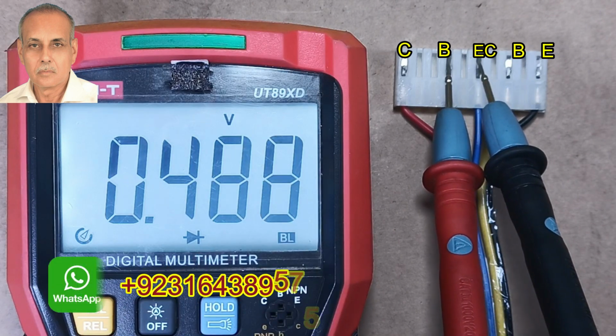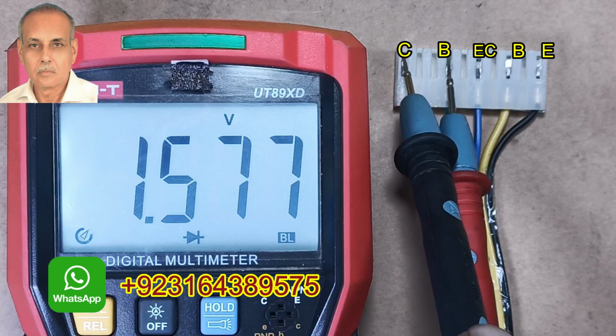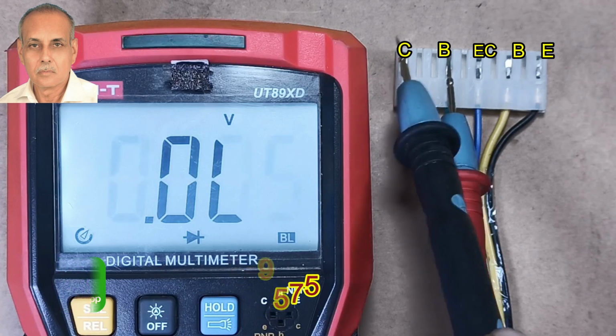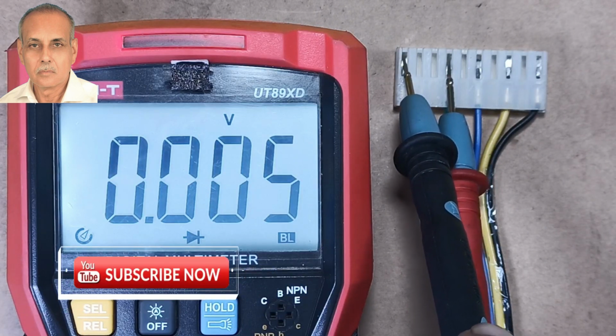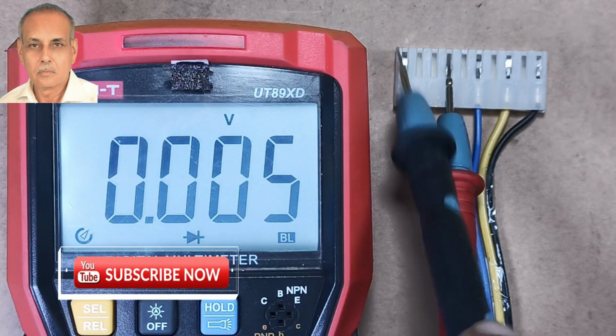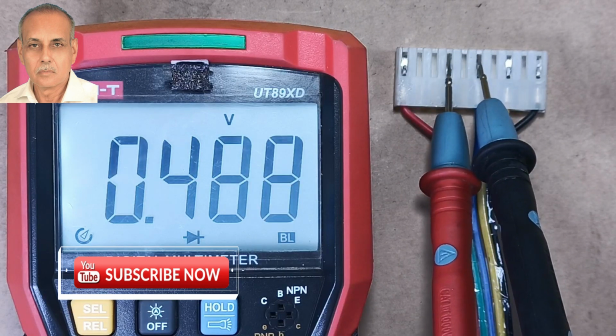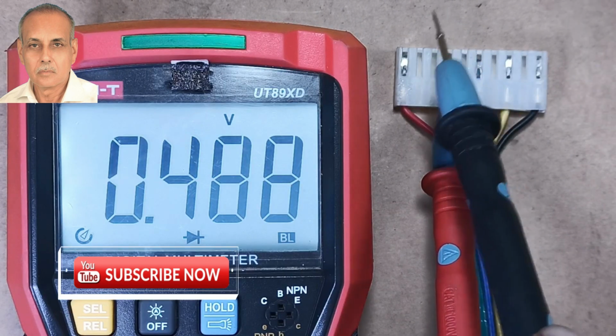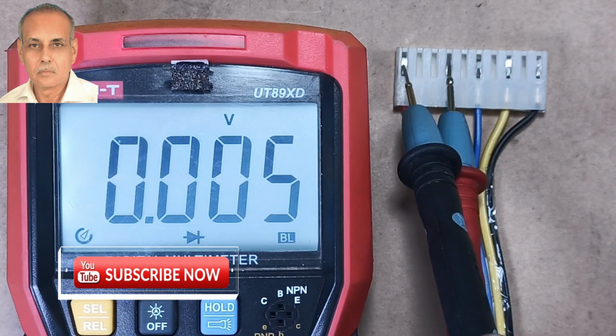Then touch the black probe to the red wire point. A reading of 0.40 volts to 0.60 volt would mean the transistor is correct, but as you can see, the meter is beeping for short circuit and showing a red light. This means that one or all of the transistors on that side are shorted.